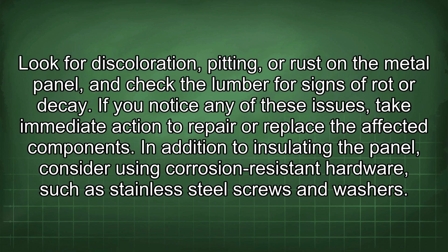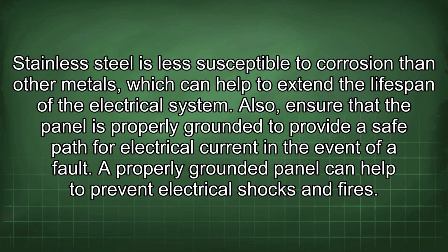In addition to insulating the panel, consider using corrosion-resistant hardware, such as stainless steel screws and washers. Stainless steel is less susceptible to corrosion than other metals, which can help to extend the lifespan of the electrical system. Also, ensure that the panel is properly grounded to provide a safe path for electrical current in the event of a fault. A properly grounded panel can help to prevent electrical shocks and fires.